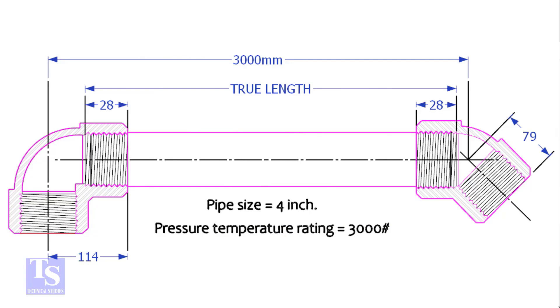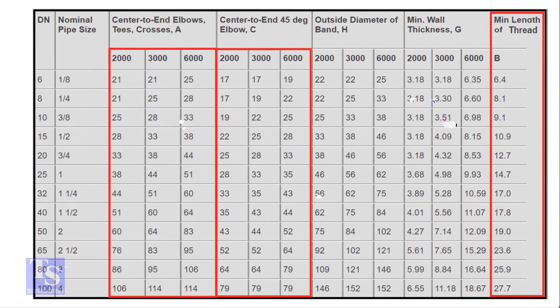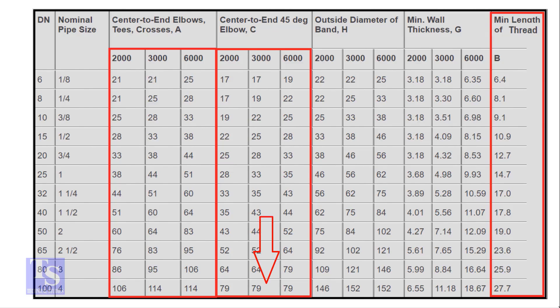Let's go through an example using 90-degree and 45-degree elbows. We're working with a 4-inch pipe, 3,000 pounds pressure rating, and a travel length of 3,000 millimeters. From the standard chart, for a 4-inch, 3,000 pounds 90-degree elbow, the take-off is 114 millimeters. For a 45-degree elbow, the take-off is 79 millimeters.